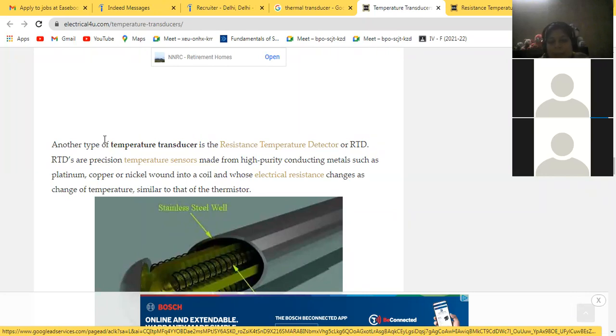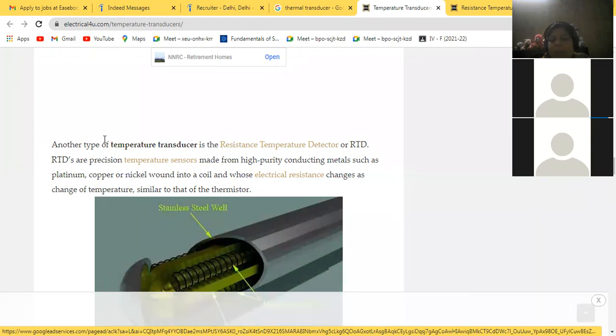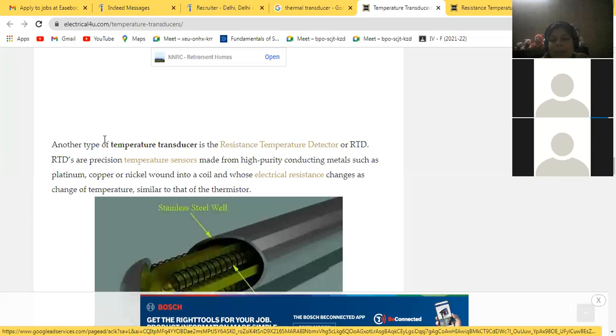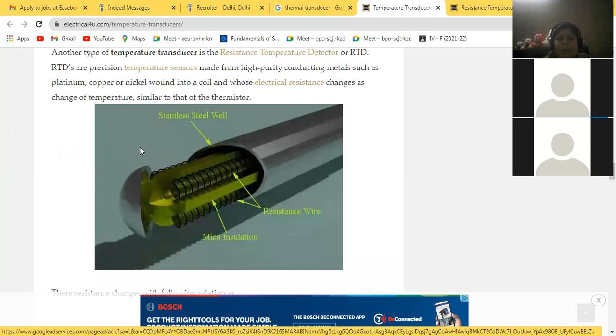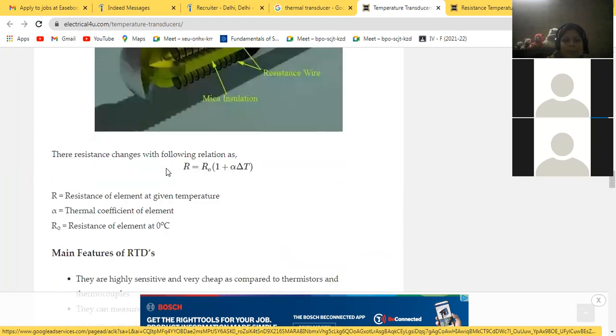Precision temperature sensors are made from high purity conducting metals such as platinum, copper, nickel wound into a coil, whose electrical resistance changes with change in temperature, similar to a thermistor. You can see this RTD: stainless steel well outside, then resistance wires, with mica insulation in between the resistance wires.